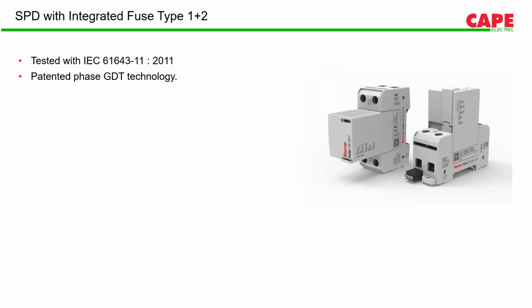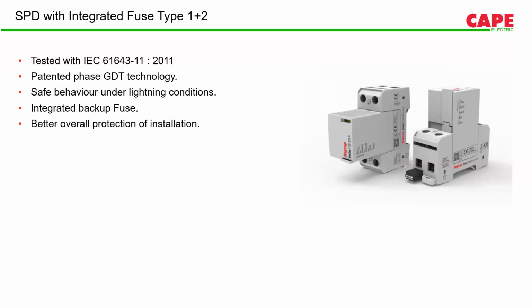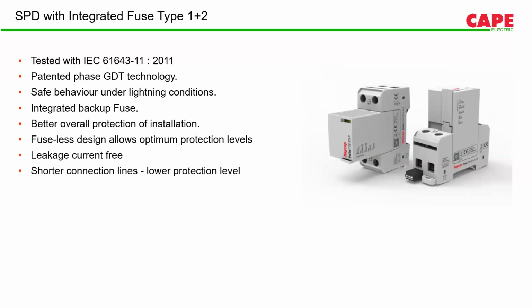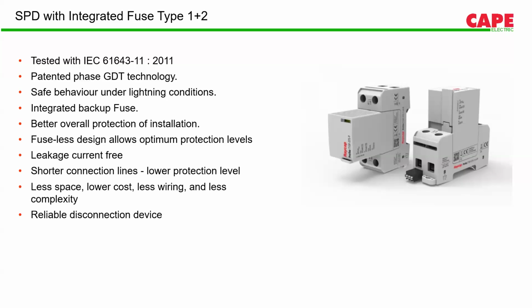The component used in these SPDs is phase GDT, which is a patented technology by CAPE. So these SPDs have safe behavior under lightning conditions. It has an inbuilt backup fuse. So even if you have an incomer rating of 4000 amp, you don't need a backup fuse. Because the backup fuse is eliminated, the cables connecting the backup fuse are also reduced, and you get better protection levels. So these SPDs are leakage current free, with shorter connection lines, of course, because of not using a backup fuse.